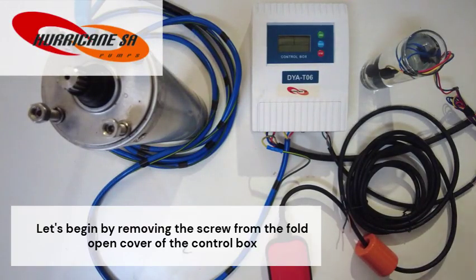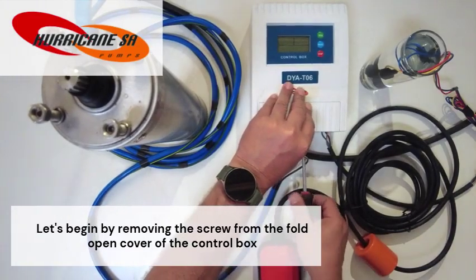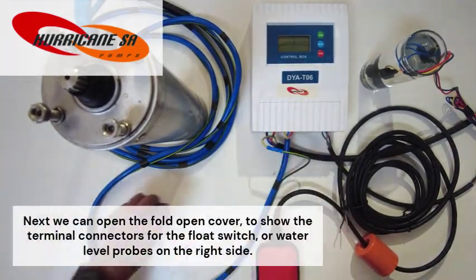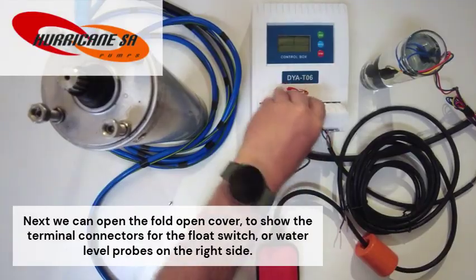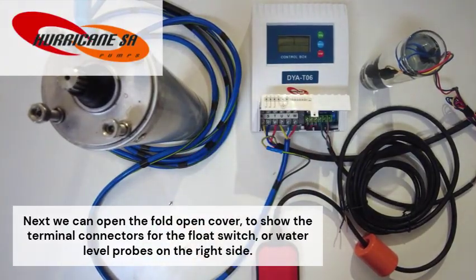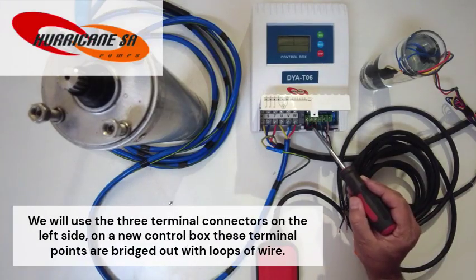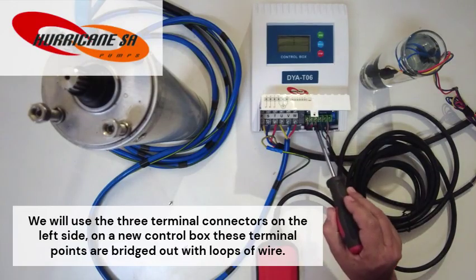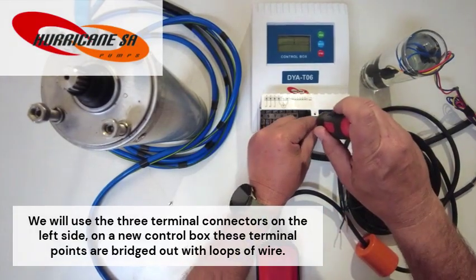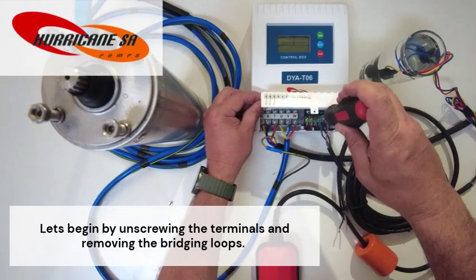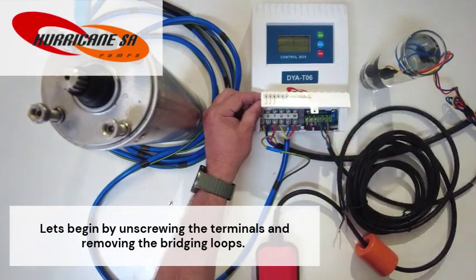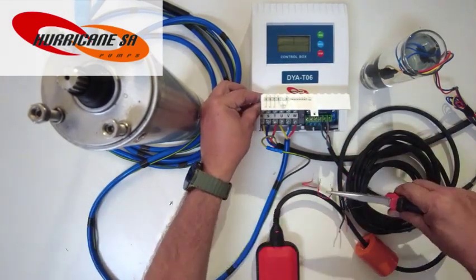Let's begin by removing the screw from the fold open cover of the control box. Next, we can open the fold open cover to show the terminal connectors for the float switch or water level probes on the right side. We will use the 3 terminal connectors on the left side. On a new control box, these terminal points are bridged out with loops of wire. Let's begin by unscrewing the terminals and removing the bridging loops.